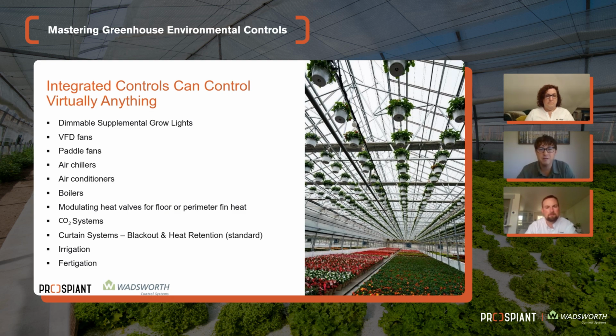VFD fans - variable speed fans - are another really popular thing in the greenhouse industry. We talked about staging controls having different exhaust fans come on at different stages. With integrated controls we can turn on exhaust fan 1 and have a different set point for fan 2. But variable speed is really nice because we're able to slowly ramp up the RPMs of that fan so we can give just enough cooling and then ramp it back down. This helps prevent overshooting, since we don't want to cool too much, have the air mix, and then go into a heating stage - it just allows for much easier dialing in.